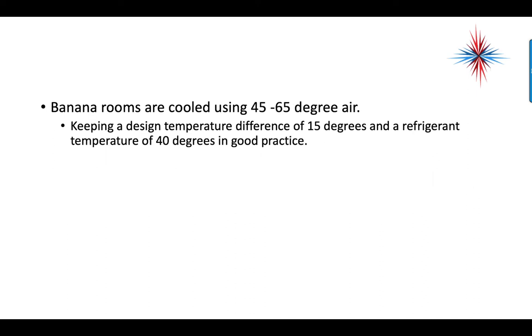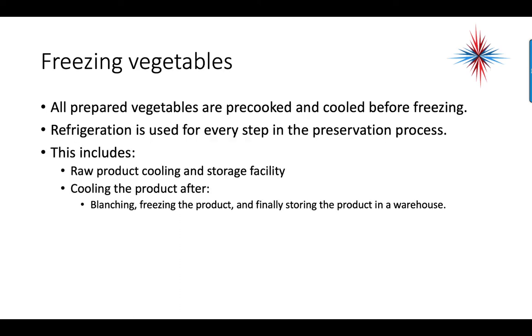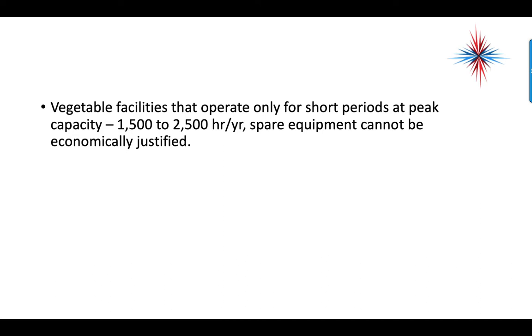Banana rooms are cooled using 45 to 65 degree air, keeping a design temperature difference of 15 degrees and a refrigerant temperature of 40 degrees. For freezing vegetables, all prepared vegetables are pre-cooked and cooled before freezing. Refrigeration is used for every step: raw product cooling and storage, cooling the product after blanching, freezing the product, and storing it in a warehouse. Vegetable processing facilities that operate only for short periods — such as orange and fruit processing plants in the south — may only operate 1,500 to 2,500 hours per year.